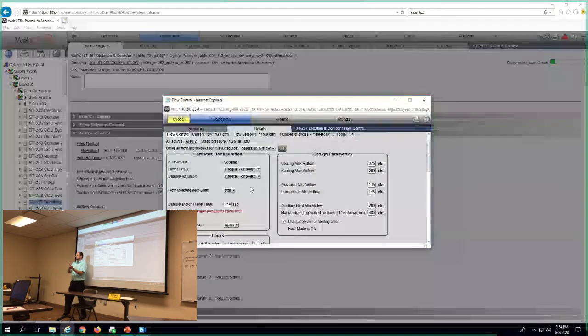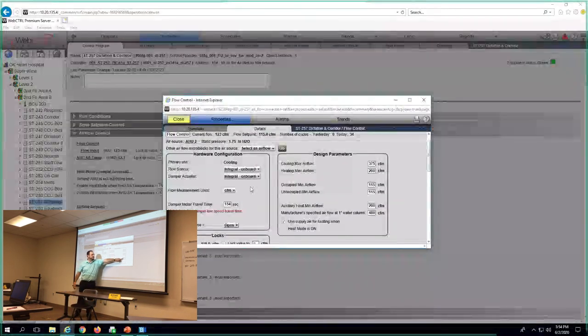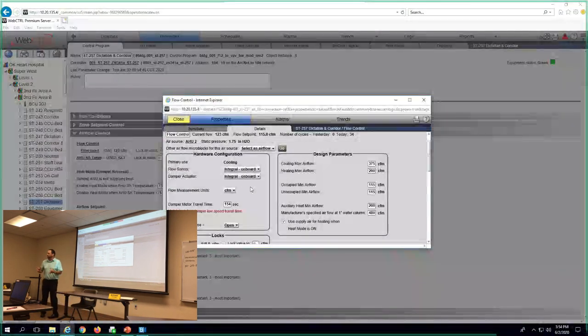When we drop into that light blue, we start calling for heating in the space. The VAV box is going to go to 200 CFM because that's the heating airflow we need to warm the space up. Make sense? Minimum. Yeah. That's the minimum. It's the same in this building because Min and max are the same, got it.